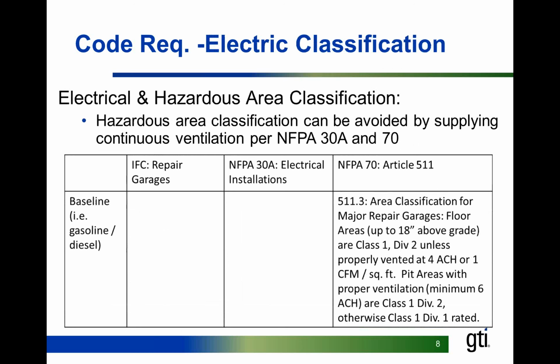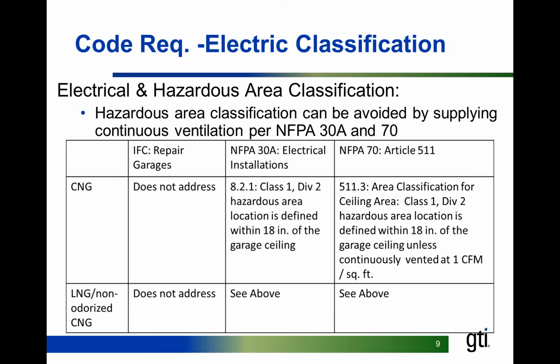The other key that the codes go over are electrical classifications. These are the baseline for electrical classifications. It's typically, for traditional fuels, the worry is for 18 inches from the ground up, because they're worried about liquid fuels. The difference for natural gas, since it's lighter than air, the concern is 18 inches from the ceiling. So often changes that need to be made to a facility are tied into the lighting or heating units that can be up in the ceiling or above maintenance bays.